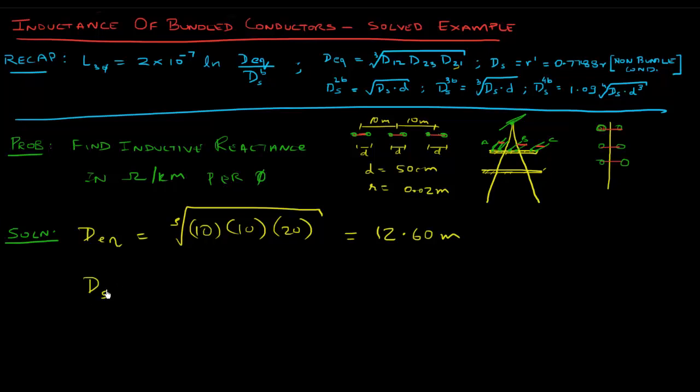What is your ds? This is a two bundle situation, so we're going to use this formula right here. So ds2b, which is this right here, is going to be - ds we know is 0.7788 times r. So let's do that: 0.7788 times r is 0.02 meters, and so that's ds. What is d? d is 50 centimeters, so that's 0.5 meters, and square root of that should give us 0.09 meters.